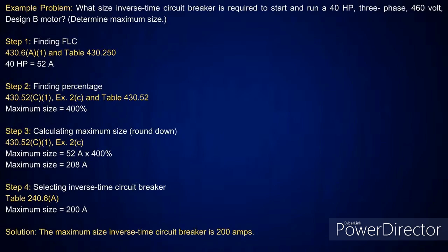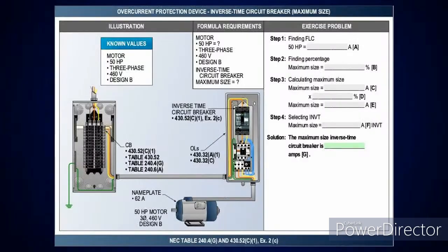And it's interesting, because I made these problems up and did this exact same thing on NEC Live, explaining the rule of thumb. If you take anything at 125% or less, go up to the next standard size. Any percentage above that, you drop down, except for the things that I discussed earlier. As I was going through that, I remember Derry said, I've never heard that before. I said, well, do the calculations and see. And as I was going through them, he said, damn, it is right, isn't it?